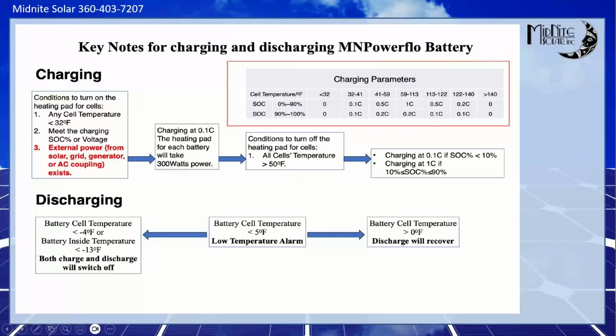So that's something that if you see that, like, why is my battery at 95% and I'm only charging it at 1,000 watts instead of 10,000 watts? Well, that's because the battery is close to full and we're throttling back to keep those high cells from getting too high. That's just what we do. That's one of the things that we spun into the BMS to sort of give that longer warranty without any loss of cycle life. So this is an important thing to keep in mind.